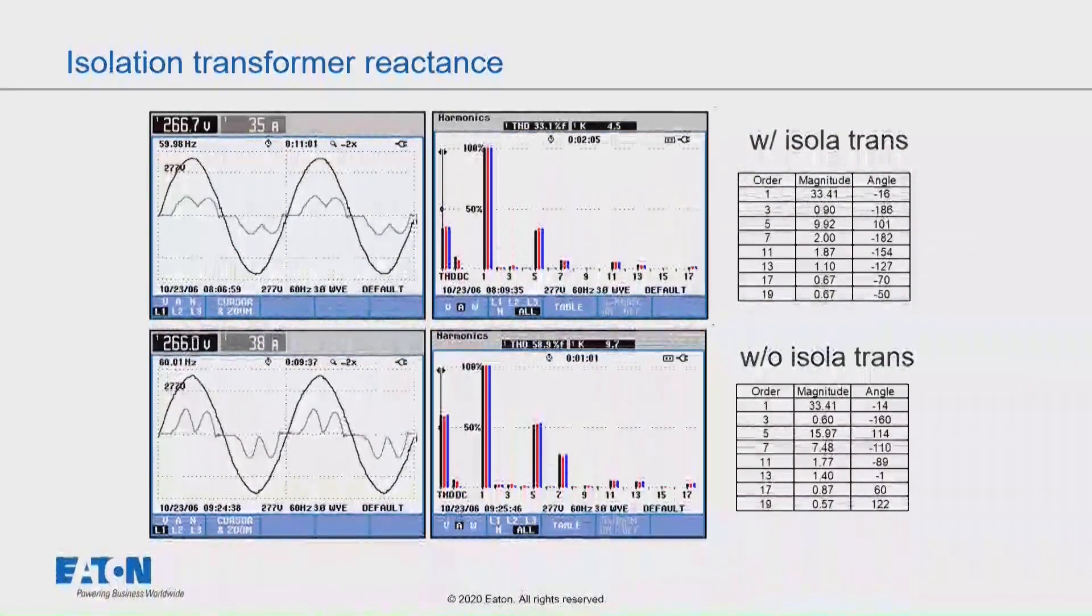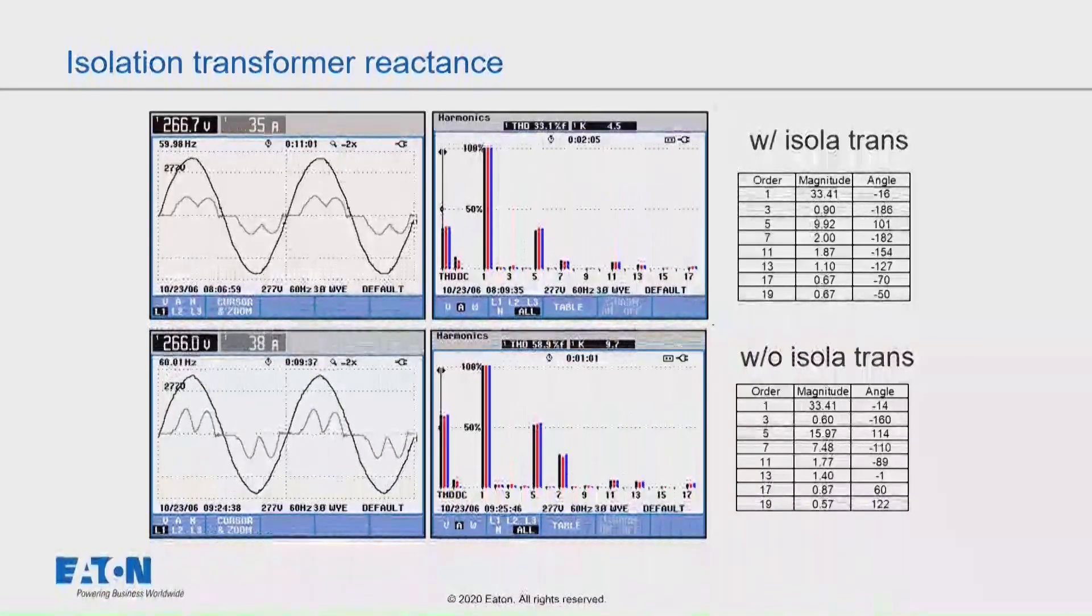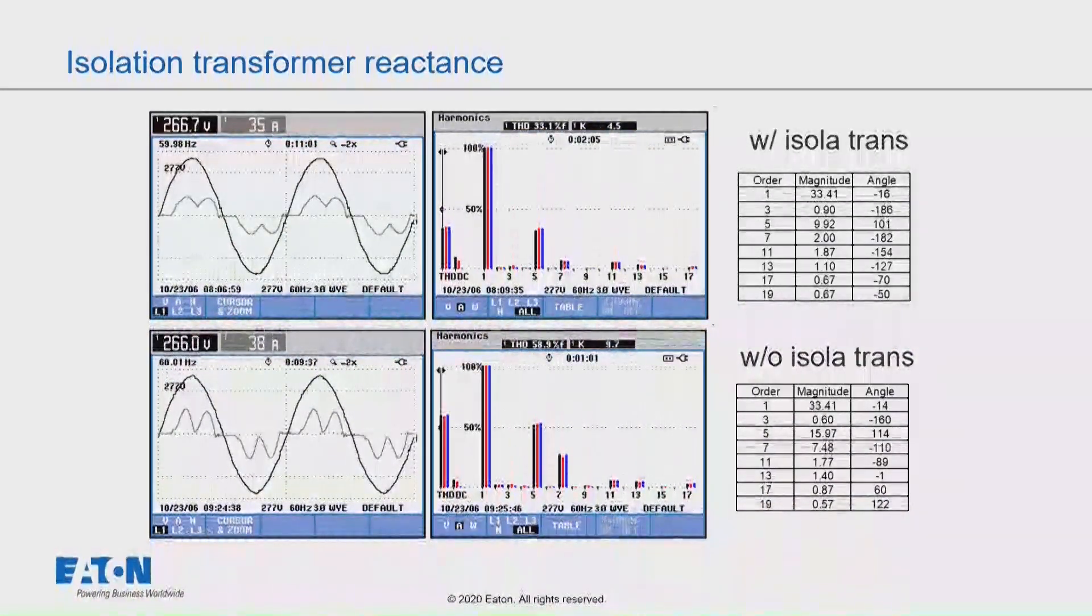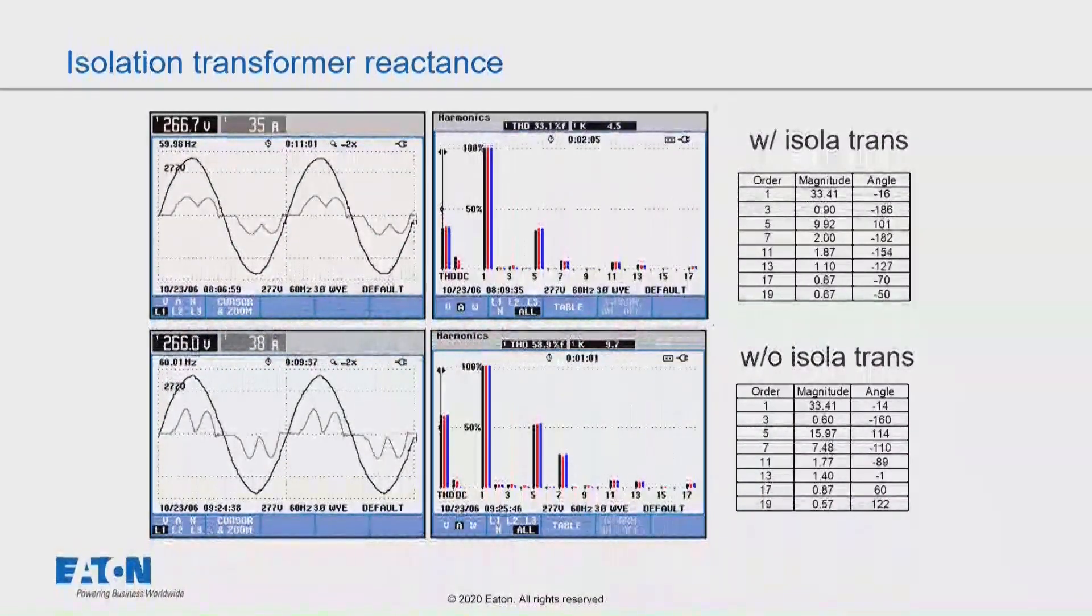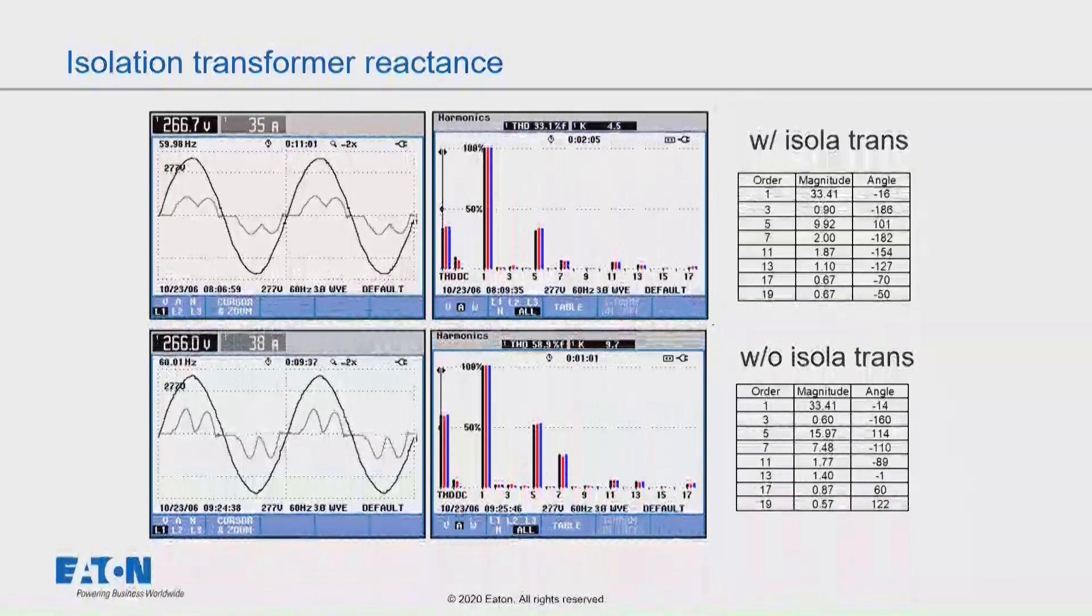Now if I had a transformer in front of my drive, what would that do? Well, the transformer impedance, a typical impedance on a transformer might be 5% or 6% impedance. That impedance acts like a line reactor does in front of the drive. So it constricts the flow of the harmonic current.